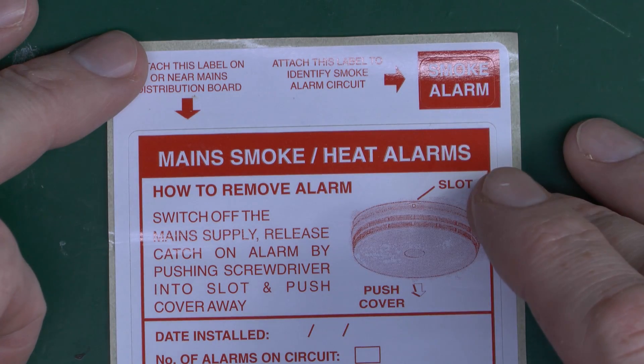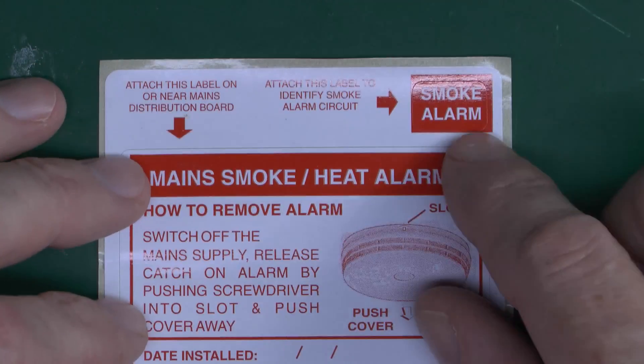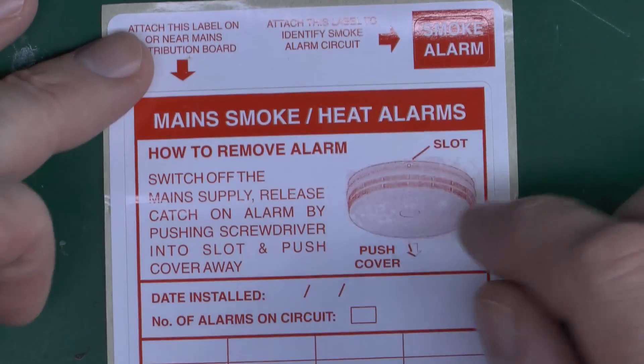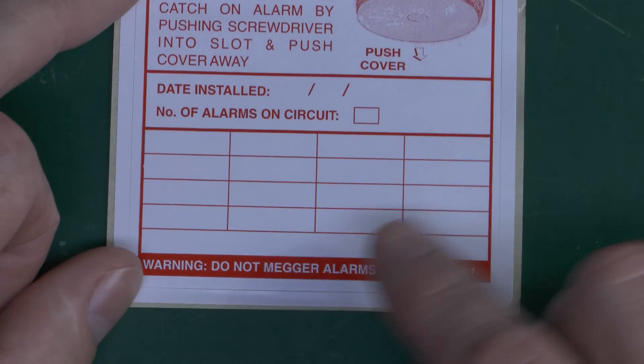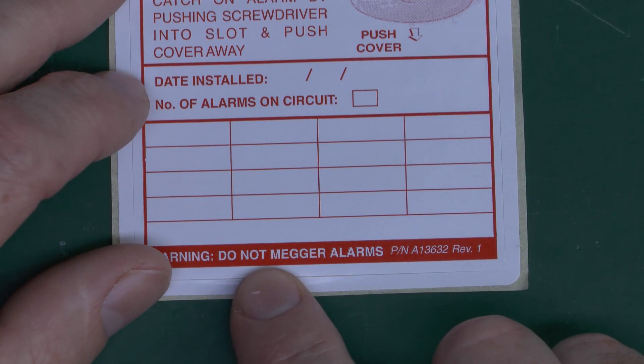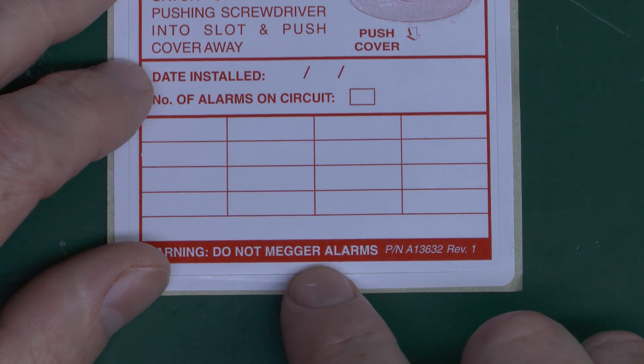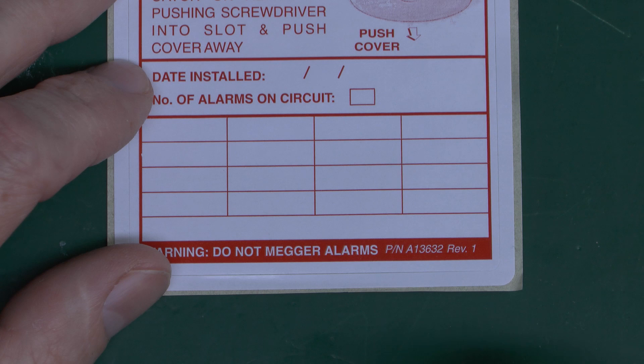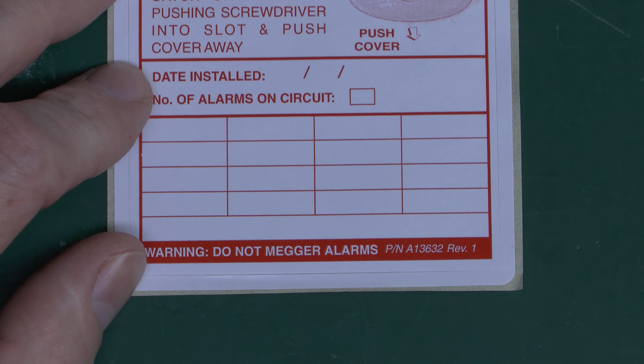Here's the label that comes with these smoke and heat alarms — it's been the same pretty much forever. The idea is you put one on the circuit breaker, this one goes on the consumer unit with the date and how many there are. At the bottom it has this warning: 'Do Not Megger Alarms.' Not really the best choice of wording, because 'megger' has come to mean an insulation resistance test. So what it means is do not insulation resistance test the circuit while the alarms are connected.